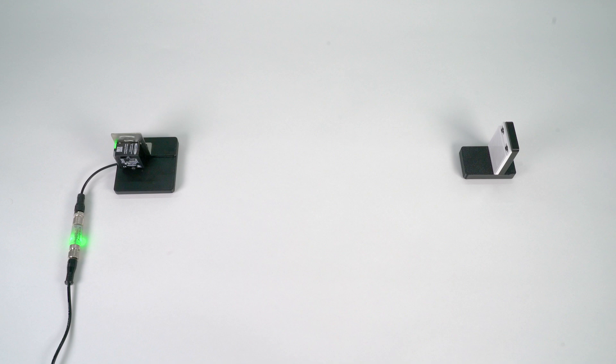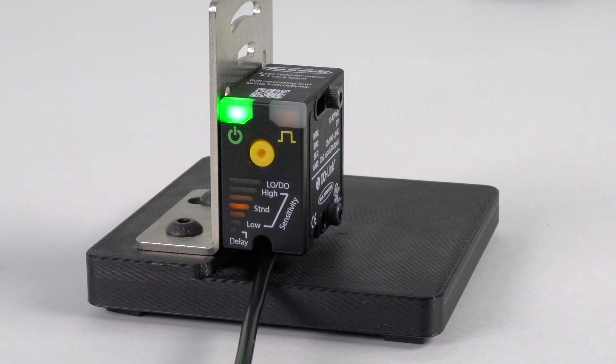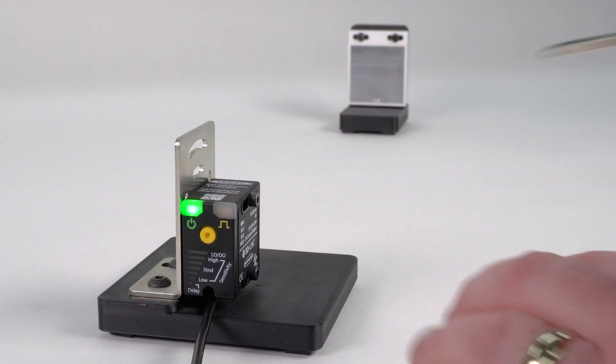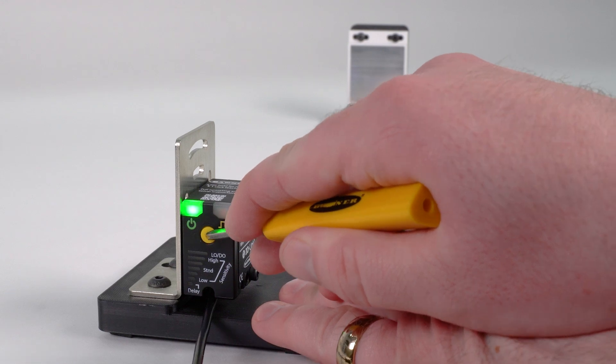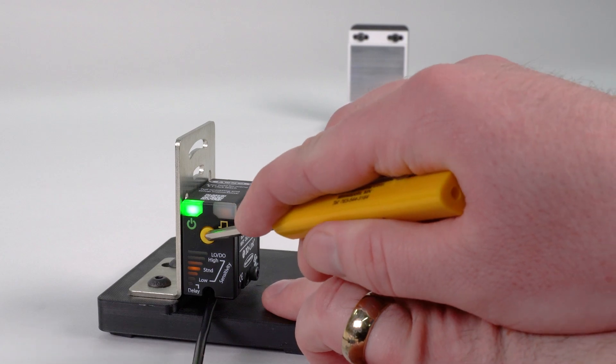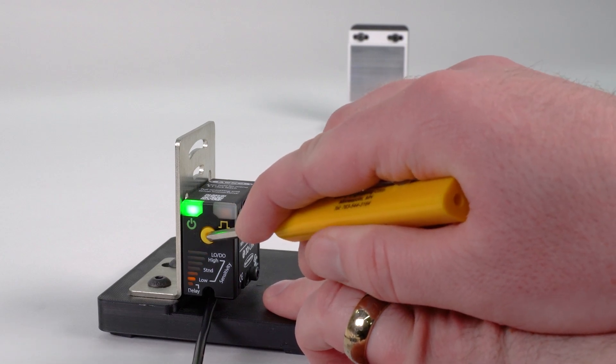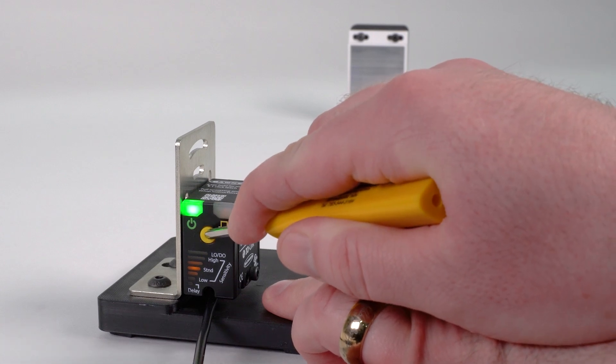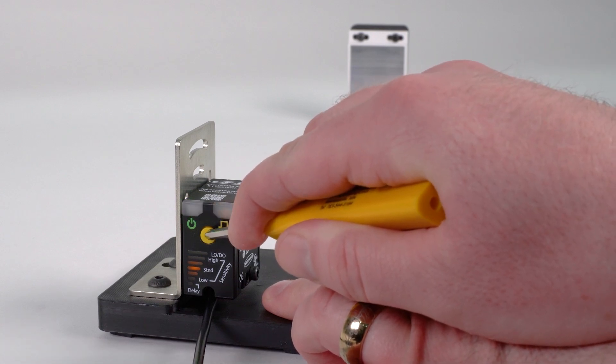The B25 also allows you to select from three sensitivity modes: low, standard, and high. To change the sensitivity, begin by putting the sensor into configuration mode and then push the button three times. By default, the sensor will be set to standard sensitivity. Press the button to toggle between the options and the bar graph will change to indicate which level is selected. Press and hold the button to select the desired sensitivity level.